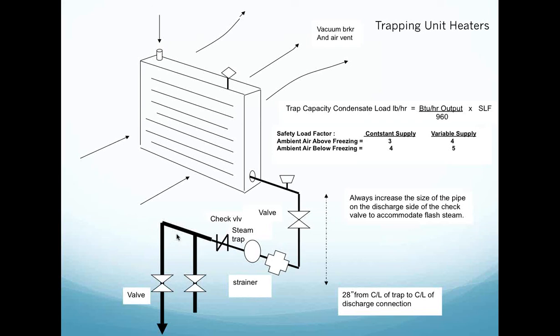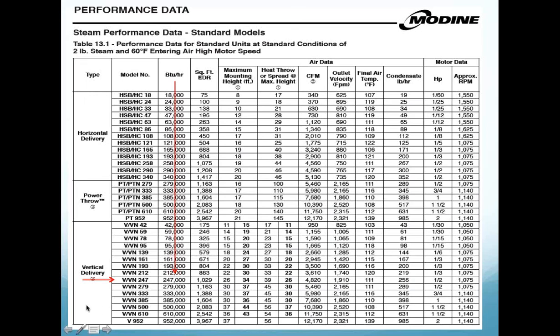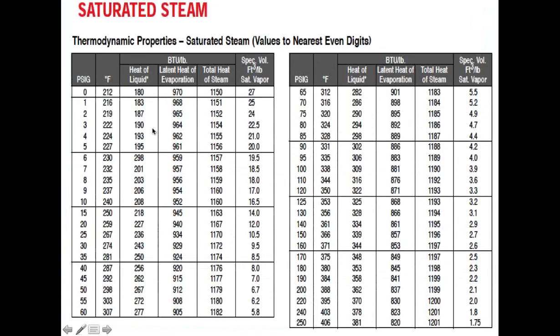And I like gravity. For a unit heater, I'm picking a size of the VN247. The capacity is 247,000 BTUs per hour, and it's really simple. You can go to the chart, and you can find these charts, and then I want you to go look at your steam chart. And let's say, for example, you're using 2-pound steam in your unit heater. It's got a latent heat of vaporization of 965 BTUs per pound.